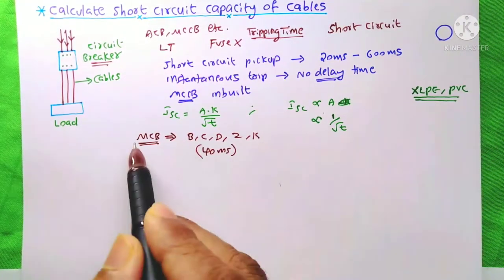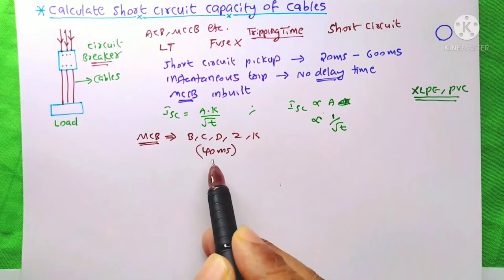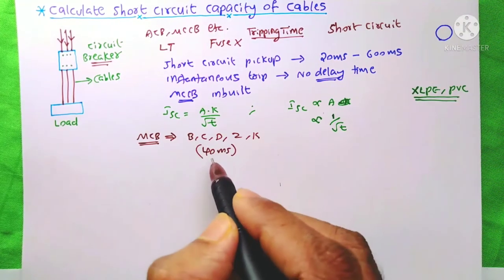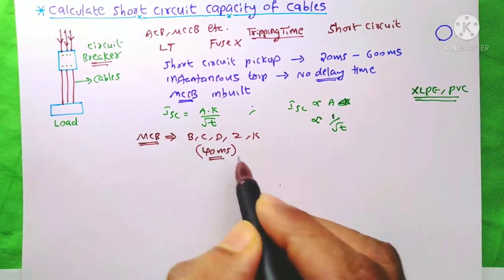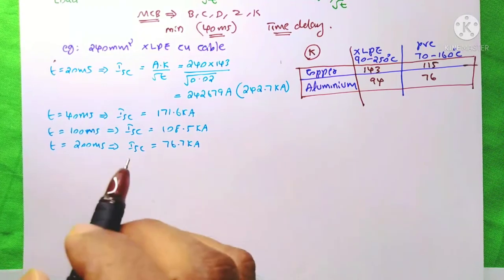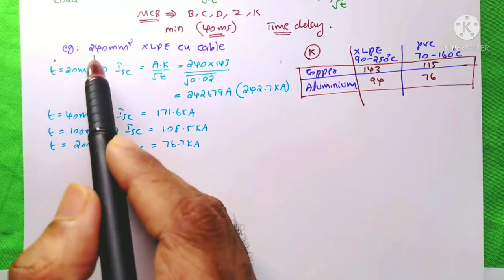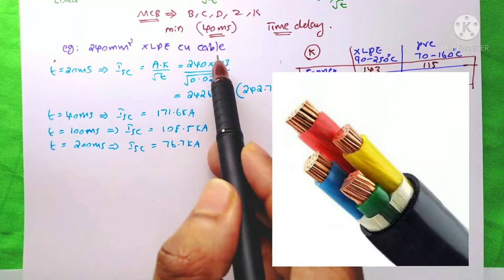But whatever the curves of an MCB, the minimum tripping time during short circuit fault is 40 ms. Here I am taking an example of 240 mm² XLPE copper cable.